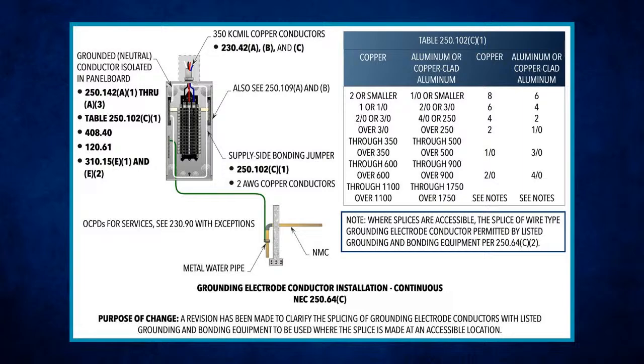Let's go with the size of service, and you take a number 8 and you take it to building steel, and then I go from building steel to bond into my ground ring. What size would I need then?